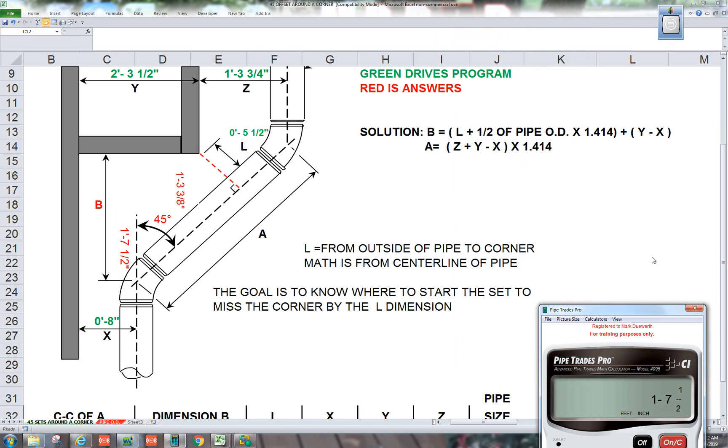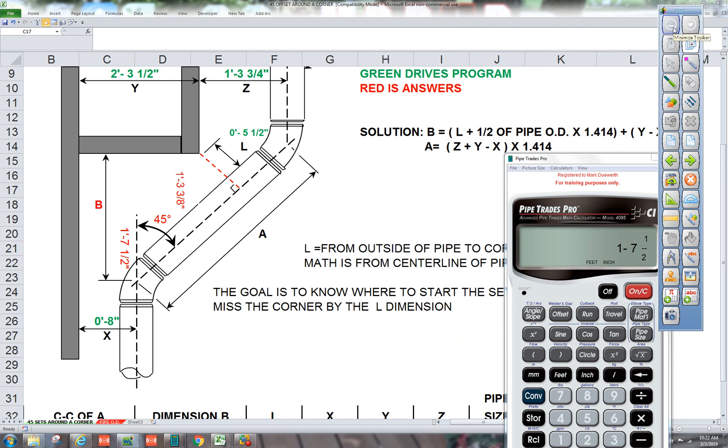Y minus X. So two foot three inch one half minus eight inches gives us one foot seven and a half. So let's draw the triangles in now. Yeah, there's a formula here, but it's triangulations everything in pipe fitting. Let's go over here.